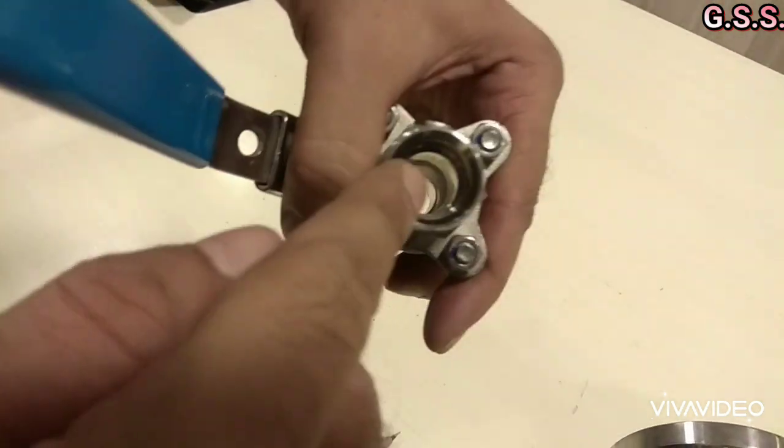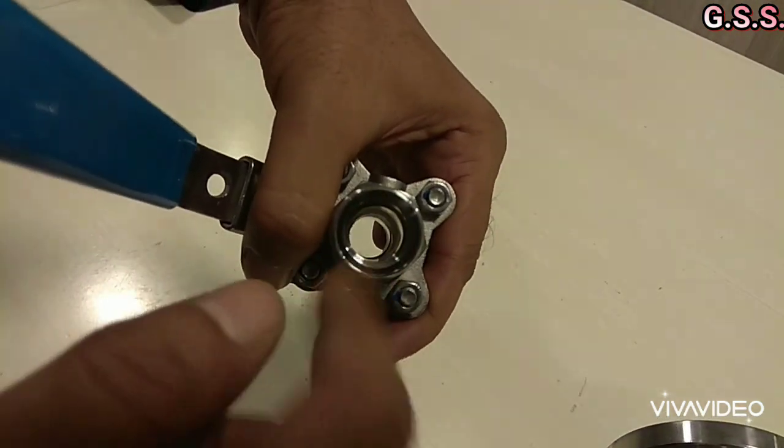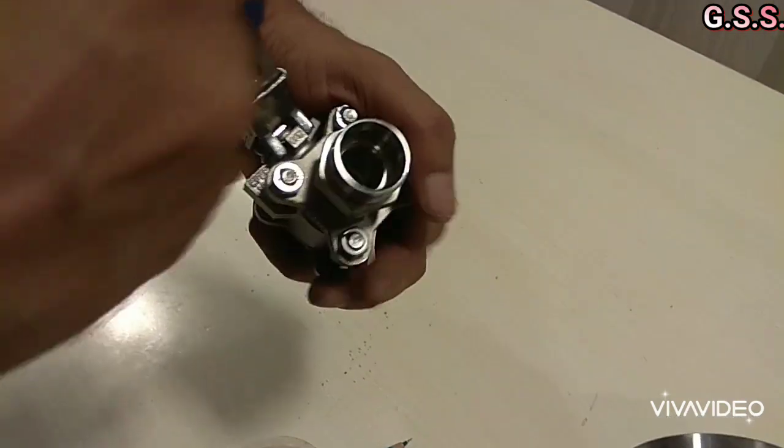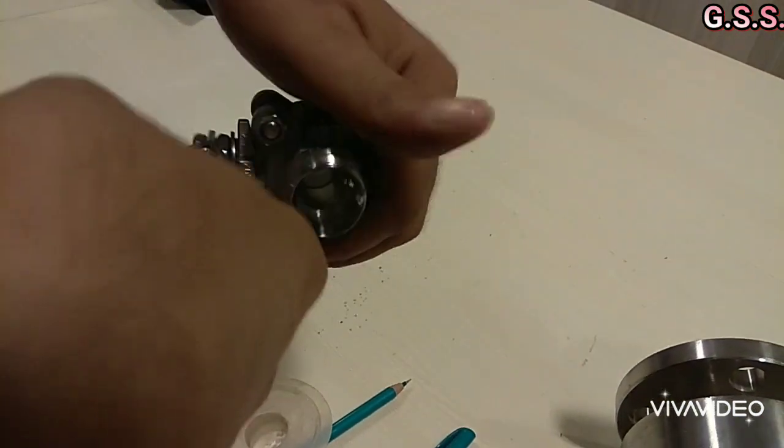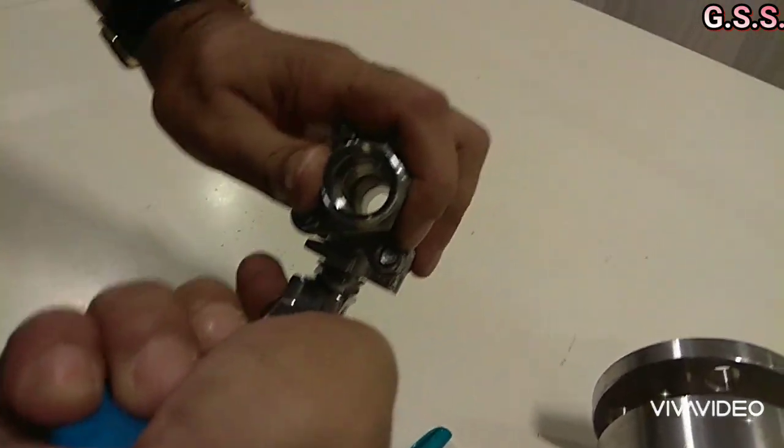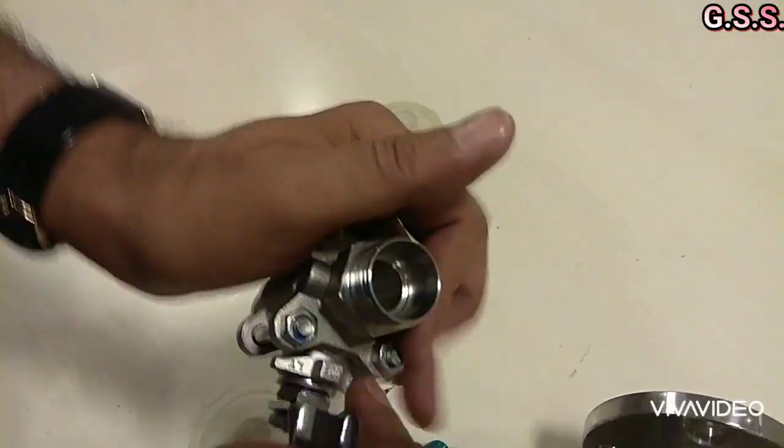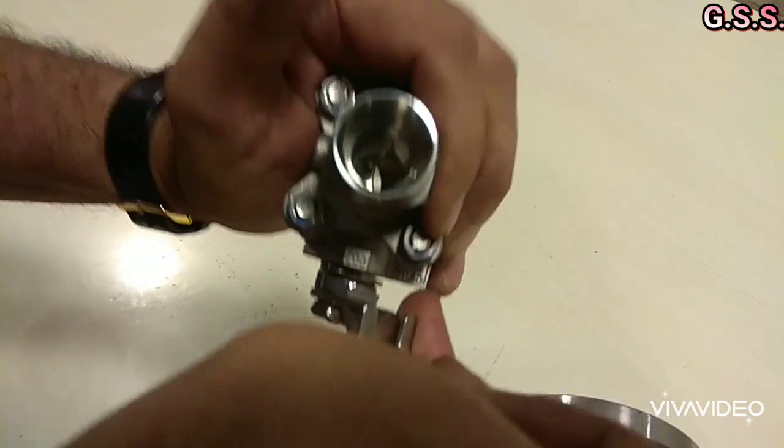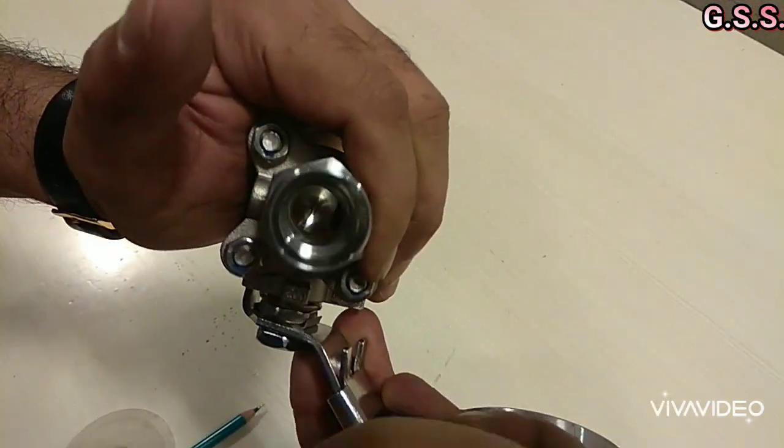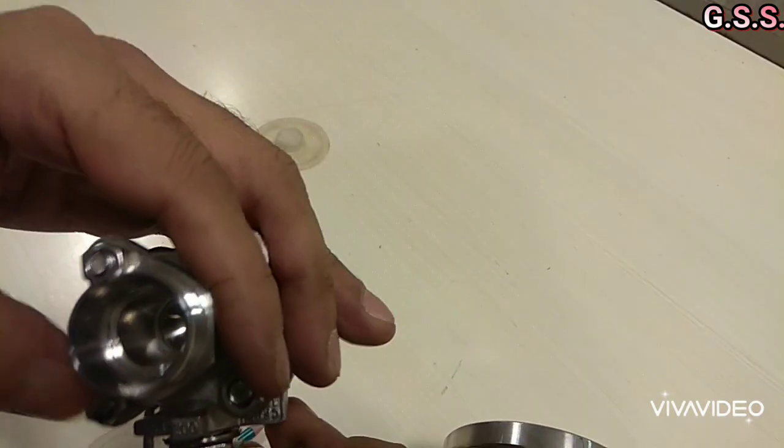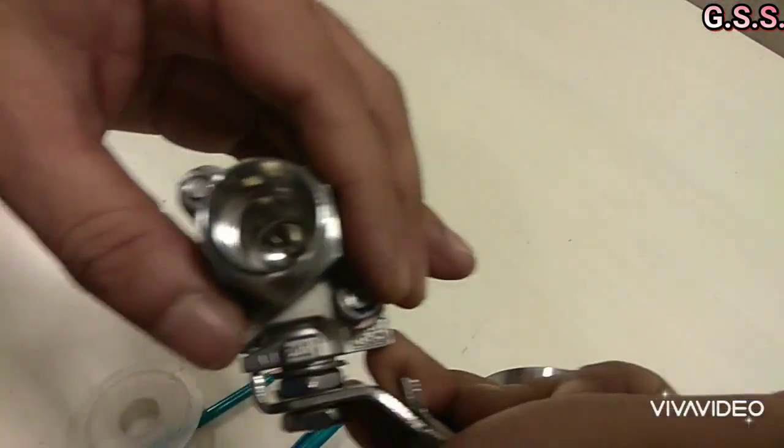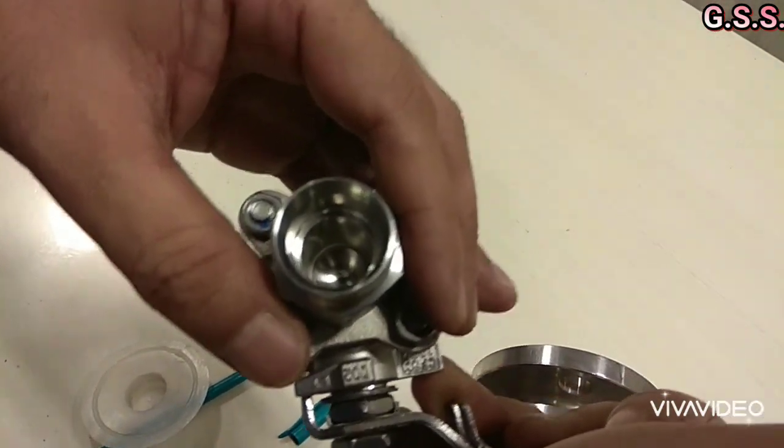And that debris, when the ball will be operated—that means the valve will be opened or closed—that debris or iron particles will be in contact with the ball and will be rubbing with the ball. So after a few months or after a few years, this type of reduced bore ball valve may have leakage.